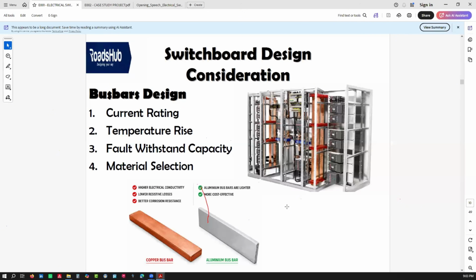If you want to set up a perfect switchboard, you need to design the system in a very critical manner for it to run in the most efficient way. So, whatever image I've used, you have these busbars supplying these outgoing breakers. What do you think the loads connected to these breakers will do to this busbar if the busbar is underrated? You can either overrate a busbar or underrate it.